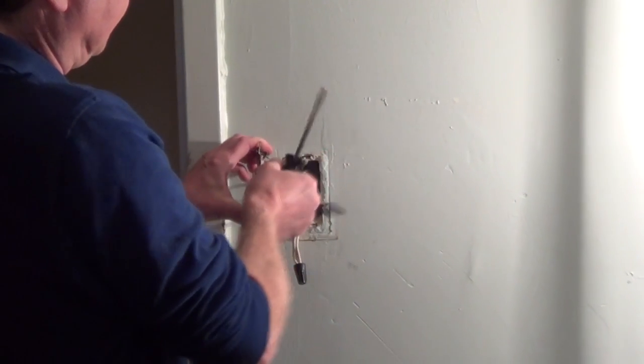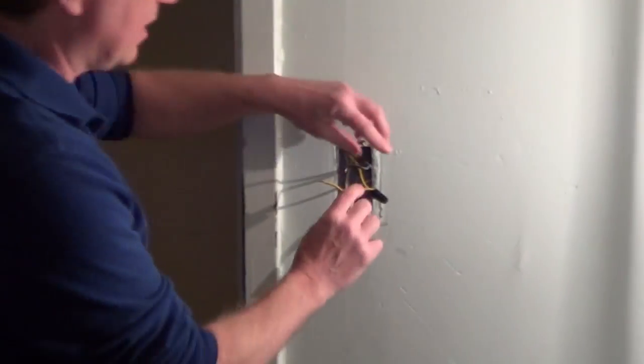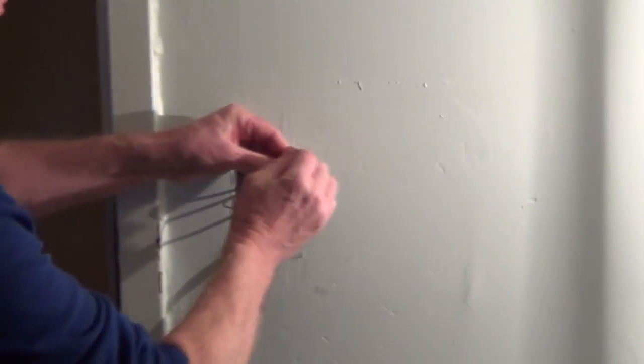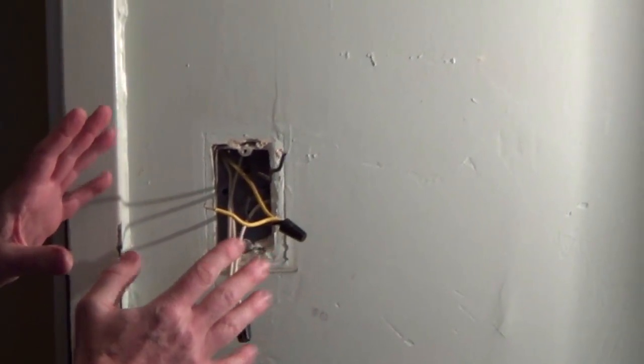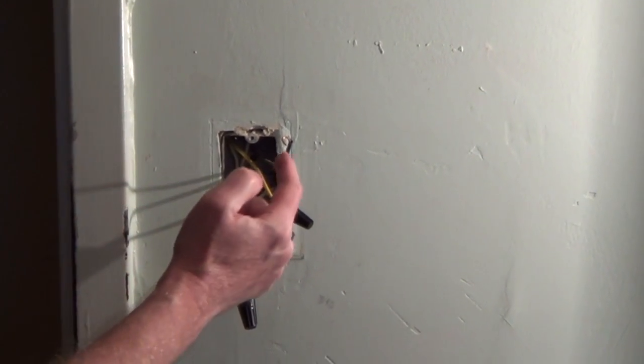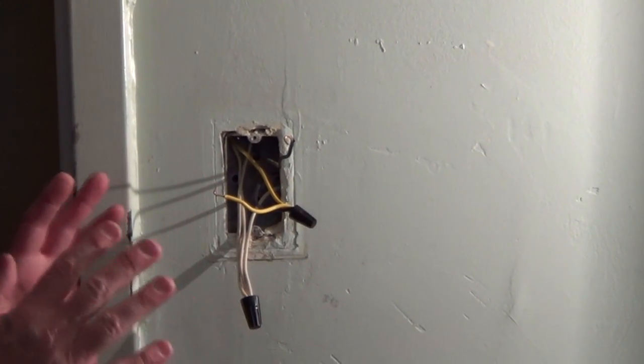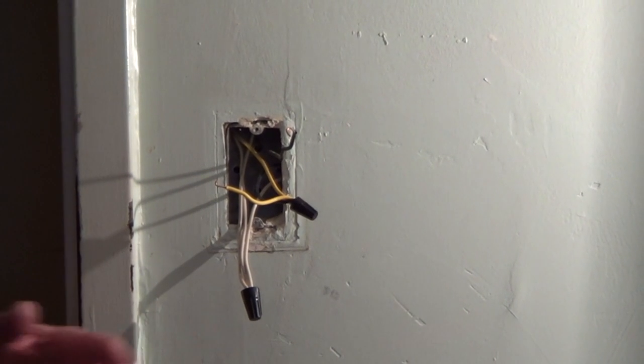In this case I'm guessing which one goes where but what we're going to do now is we're going to separate these wires, make sure they're not touching anything, we're going to turn the electric back on and then we're going to test each wire so that we can confirm which one is coming from the service panel.